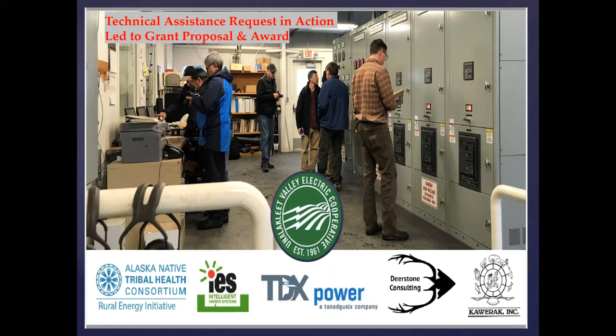Our award and project outcomes are on this slide. The task force identified two primary changes we could implement to get to these outcomes. By increasing our voltage in part of our system and making switchgear and SCADA control changes, we expect to increase our wind penetration from about 25% to 40%, and save approximately another 44,000 gallons of fuel annually. We'll also stretch the intervals of annual maintenance and overhauls for our diesels, reducing diesel maintenance costs and emissions, and becoming less dependent on diesels.